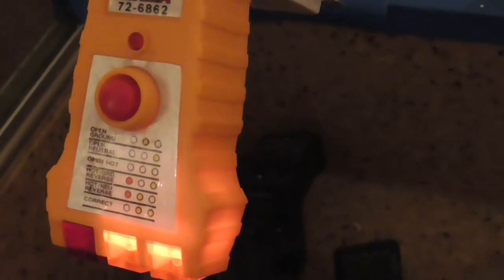Both wires have been swapped, I really didn't swap them, I just swapped the position of the outlet. When we look down over here now, we have no light on the left, we have two lights on the right. And if you look down on the bottom, no light and two lights, two yellow lights and no light on the left is correct. So this outlet is now wired properly.